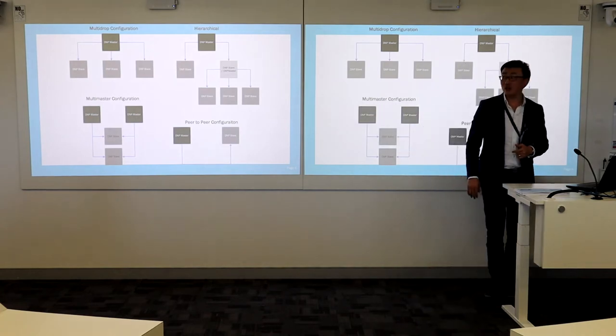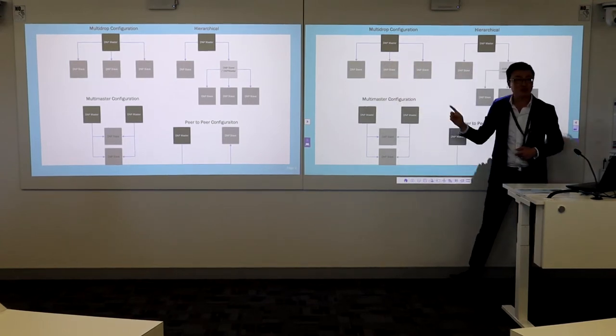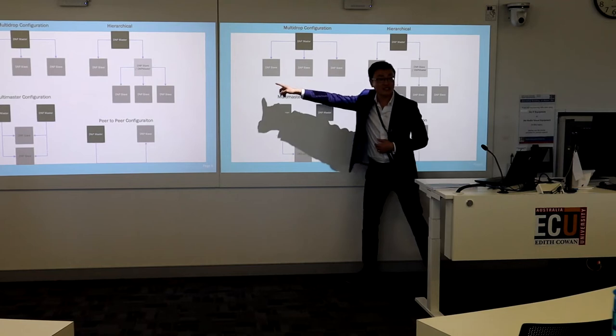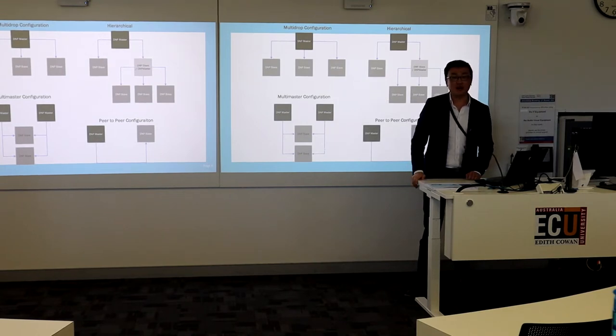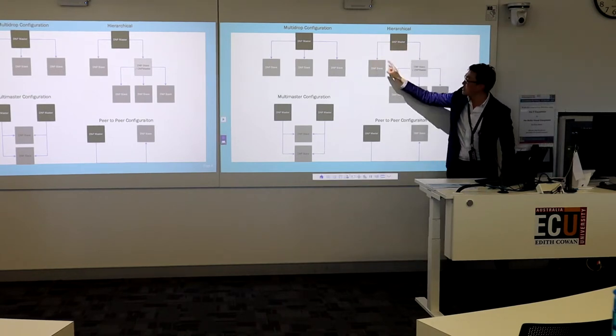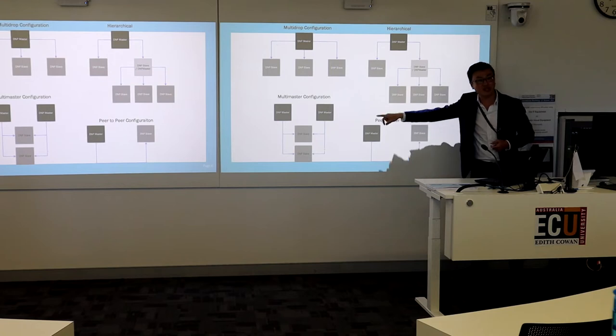Now we're going to go into the communication hierarchy of DNP3. The conventional DNP3 is called multi-drop — a DNP3 master talking to multiple slaves. The slaves can be SCADAPack RTUs or any other intelligent electronic devices with a DNP3 slave driver, all acting as DNP3 slaves. That's a very common structure and I believe you have that structure in your control systems lab. We also have another hierarchy: on top we have a DNP3 master multi-dropping to two slaves, and those slaves can each act as a DNP3 master and multi-drop further down to more slaves — growing like a tree.